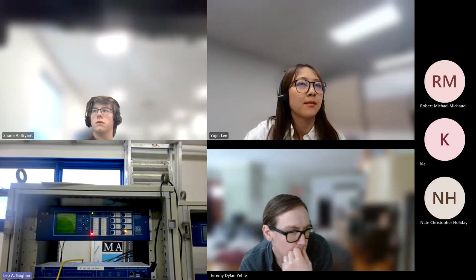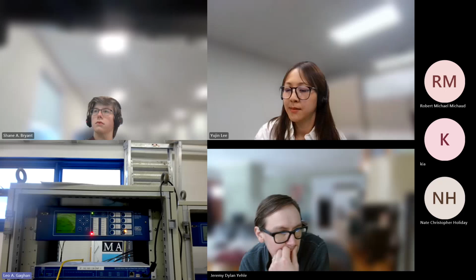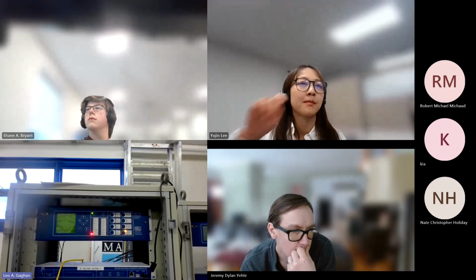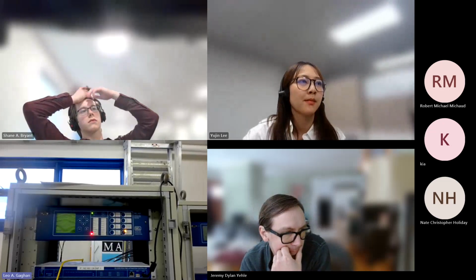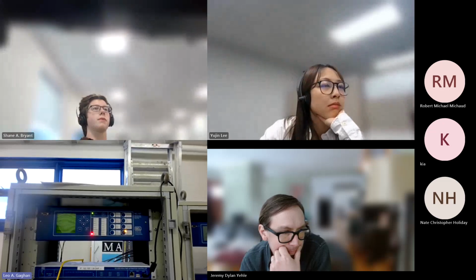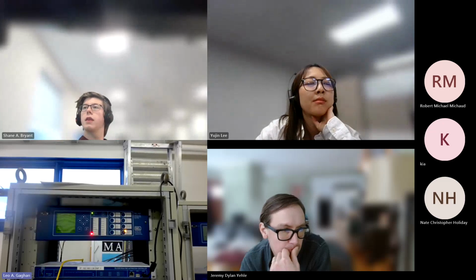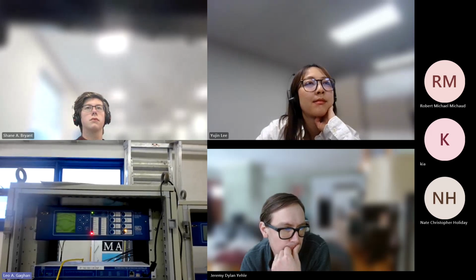It comes to the internal closing logic. This is all internal. That'll get processed and then go to that output over here, which is what's actually wired. So there's a diagram of the relay, just like with internal bits. This is what's going on inside of the relay. Everything here is what we can program. And then this dotted line, that's what's called internal logic. You have to go to the instruction manual, and the manufacturer has provided some functions that you can interact with. So, we'll roll through this. I won't highlight any of that other logic, but I do want to talk about some of the other functions that played into it.